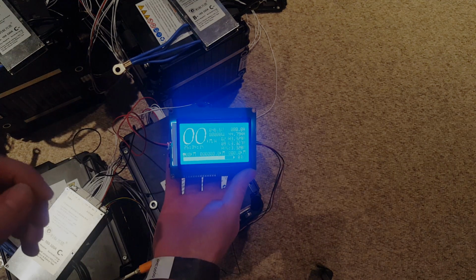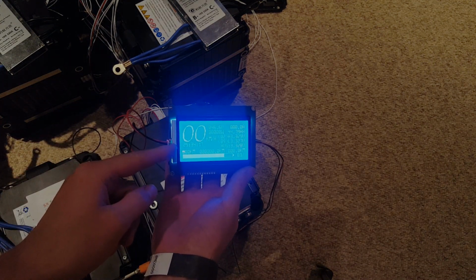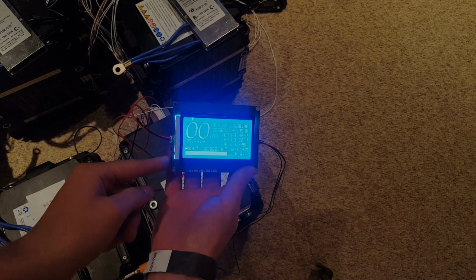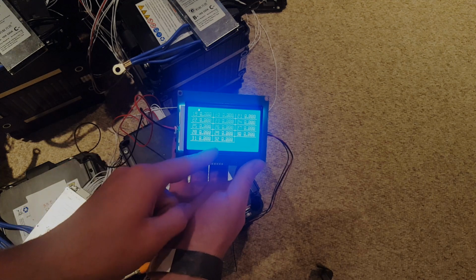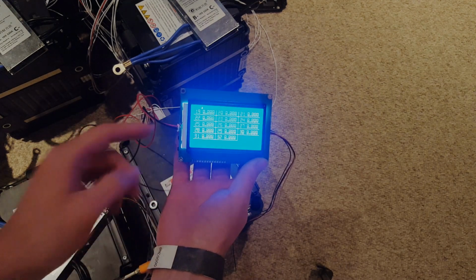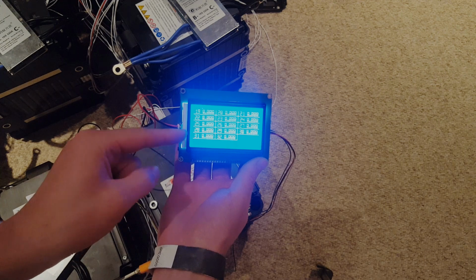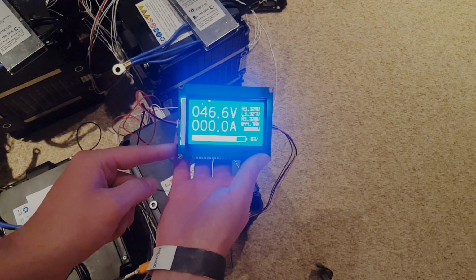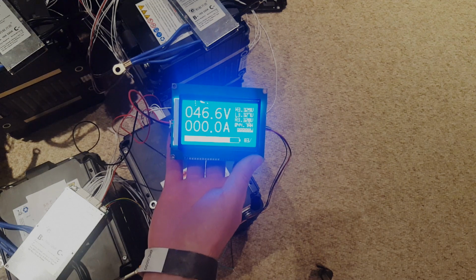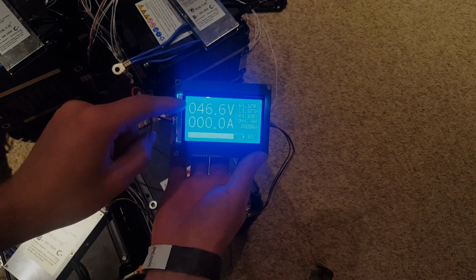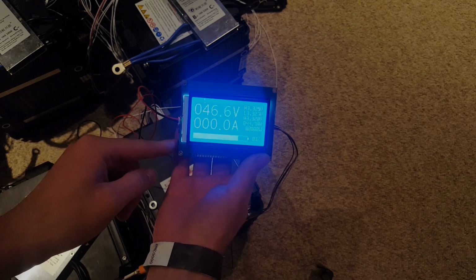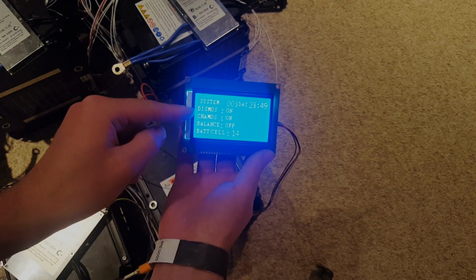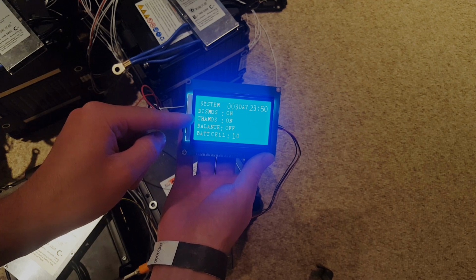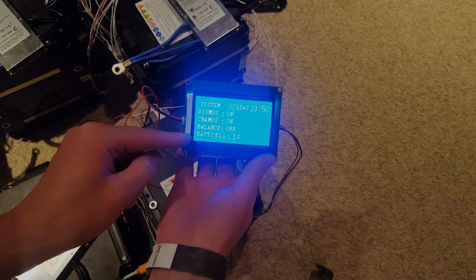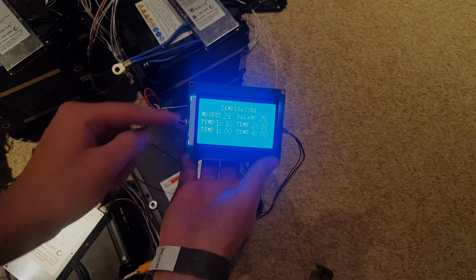I also figured out that these battery screens have more views than what I showed earlier in the video. There's this main screen here, and when you scroll down, it'll give you all of your individual battery voltages up to 32 cells, even though this will only go to 16. It's probably a generic software. And then if you hit down again, it'll go to this screen, which is probably the one we're going to use because it gives us the most information for our application. It's not so cluttered. And then if you keep going, it'll start giving you whether your discharge MOSFETs are on, your charge MOSFETs, whether it's balancing, the number of cells, and temperatures.